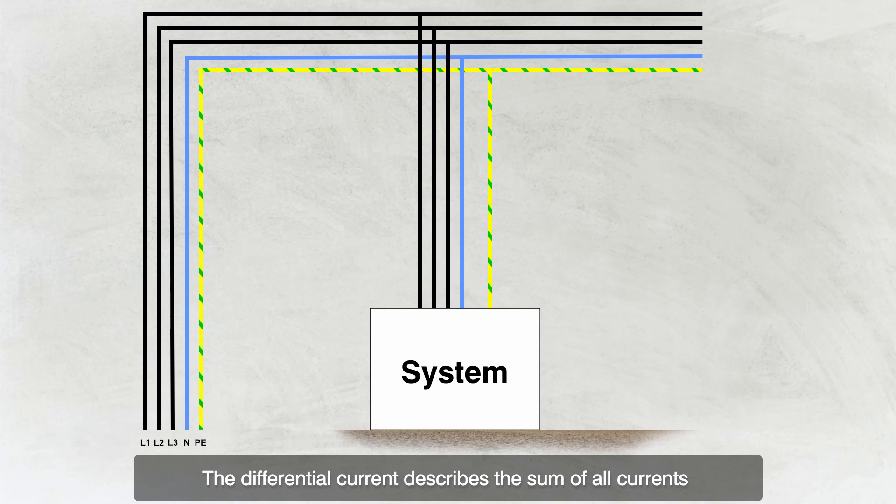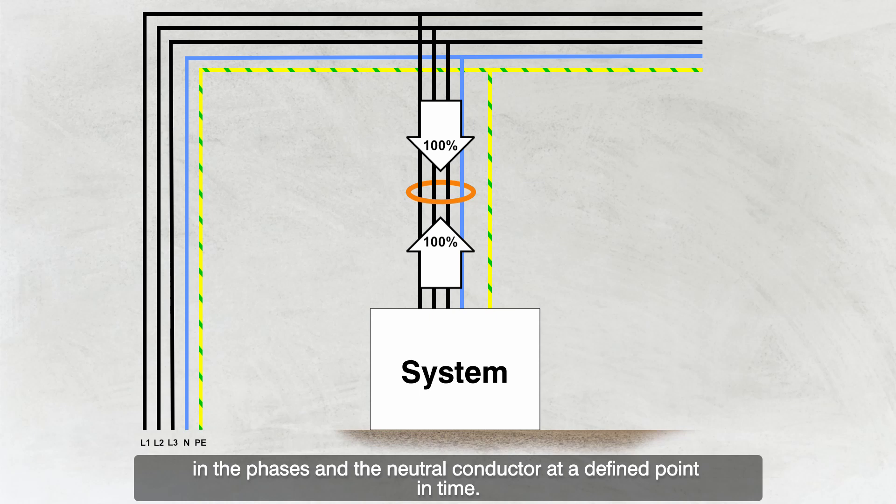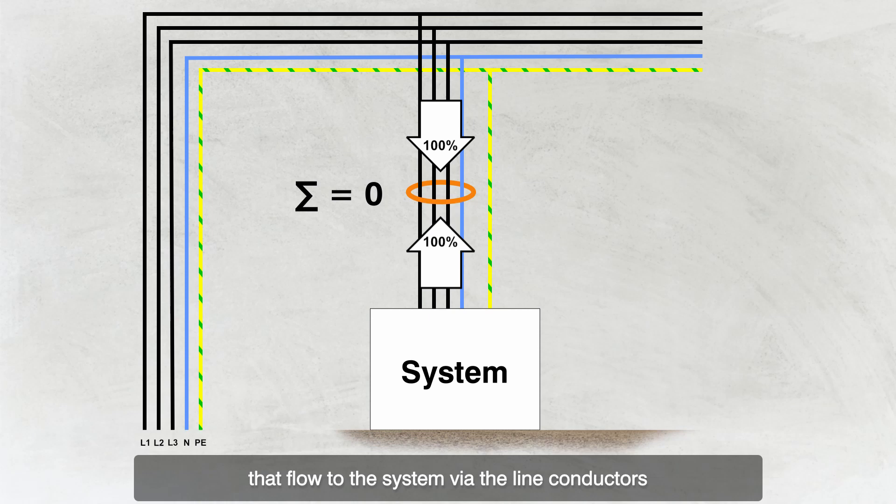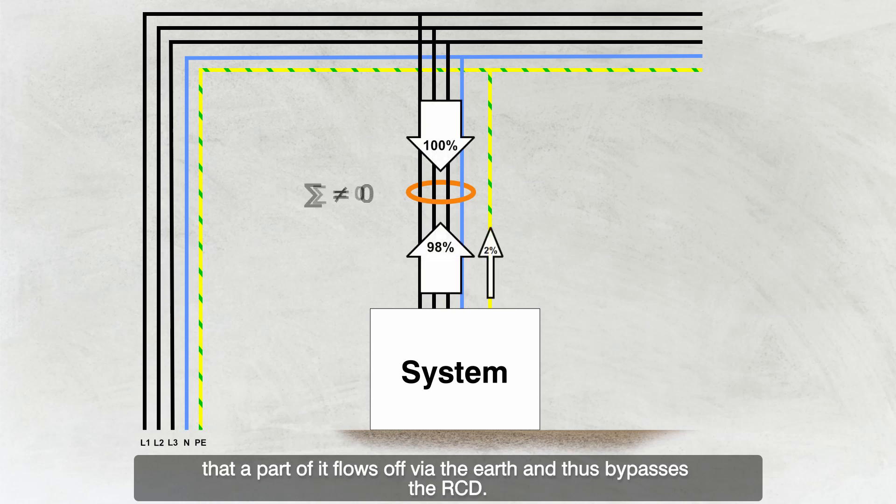The differential current describes the sum of all currents in the phases and the neutral conductor at a defined point in time. Ideally, this value is zero, because all currents that flow to the system via the line conductors also return this way. If this value is greater than zero, it means that a part of it flows off via the earth and thus bypasses the RCD.